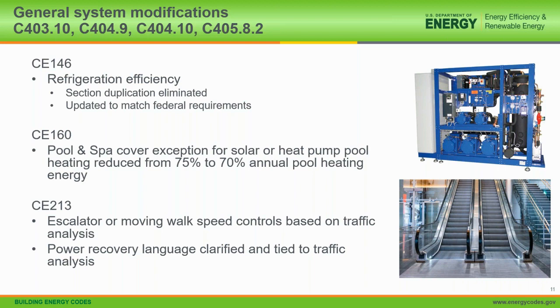CE 213 relates to escalators or moving walk speed controls and also power recovery or regenerative, where you actually recover energy when an escalator is going down. Those requirements were in there before. This adds the requirement to do a traffic study. Now, frankly, the code language is not very clear on exactly what that means as far as when this would be required or when not. I guess the assumption is the traffic study would actually look at cost effectiveness and when it's appropriate to add these speed controls. We anticipate that perhaps some guidance will be coming forward on that, but just to point out, it is an area that could use some more clarification and will require jurisdictions to make some determinations about how to interpret those traffic studies.